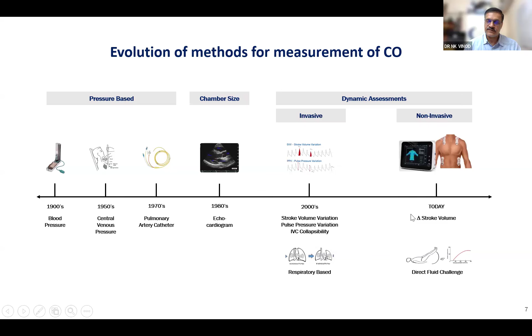Amongst the non-invasive measures of cardiac output monitoring, we have the bioimpedance and the bioreactance. Basically, they share some of the principles, but in some ways they are different. The thoracic electrical impedance, bioimpedance, is based on the assumption that changes in intrathoracic blood volume during the cardiac cycle induce changes in the electrical conductivity of the thorax, and that are mainly related to changes in the aortic volume. It is based more on amplitude modulation. And these monitors face certain technical and pathophysiological limitations due to extraneous electrical interference, making them less suitable.